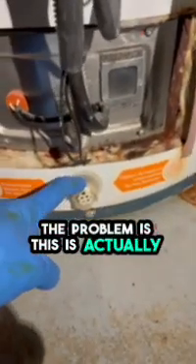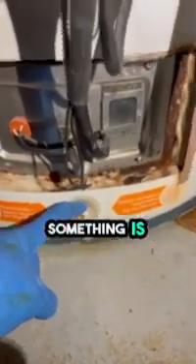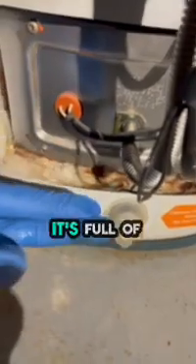But this isn't even the problem. The error code is saying something is wrong, and when I put my hand inside here, it's full of water. This whole thing is just full of water — the tank rusted out from the inside. It's leaking. You have to shut this off, shut this off.